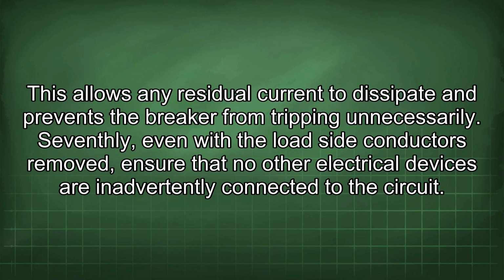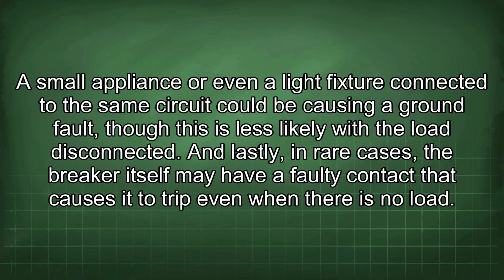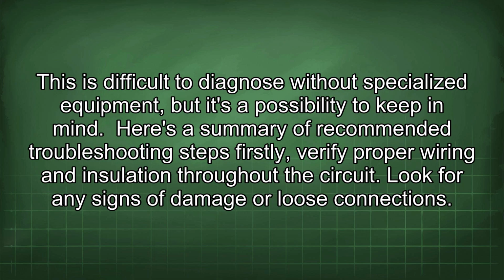Seventhly, even with the load side conductors removed, ensure that no other electrical devices are inadvertently connected to the circuit. A small appliance or even a light fixture connected to the same circuit could be causing a ground fault, though this is less likely with the load disconnected. And lastly, in rare cases, the breaker itself may have a faulty contact that causes it to trip even when there is no load. This is difficult to diagnose without specialized equipment, but it's a possibility to keep in mind.